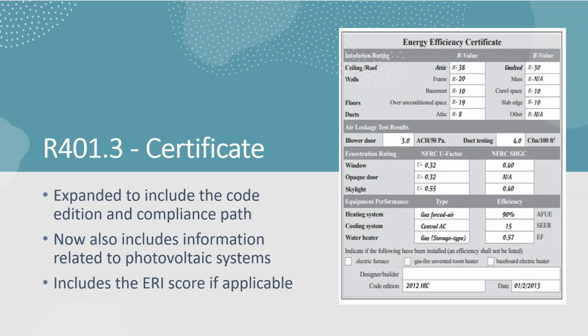In my opinion, also, does this meet and/or exceed what was permitted? So if you look at the permit and it says that your cooling system was 15 SEER and you see this certificate and the person in the field wrote down 13 or 14, that changes everything. If it says in the model that it was a gas furnace and now it's a heat pump, that changes everything. If it says the walls were R15, and the guy wrote 13 on this certificate, that changes the compliance documents. It should be re-verified to show compliance. So that's why you have a projected at the beginning and you have a certified, verified, confirmed at the end, to verify that everything that was supposed to be done has been done and meets or exceeds the requirements of the code.